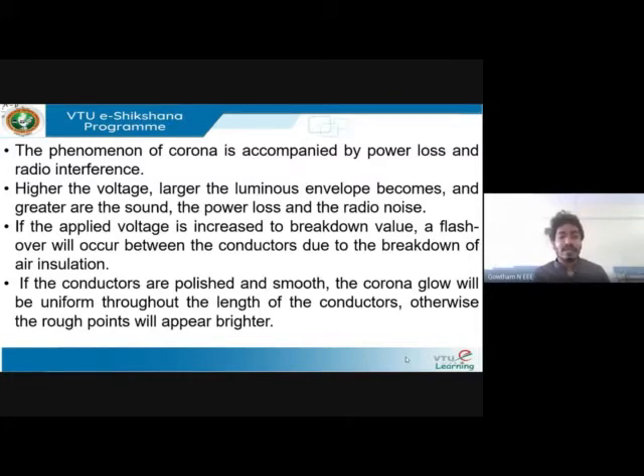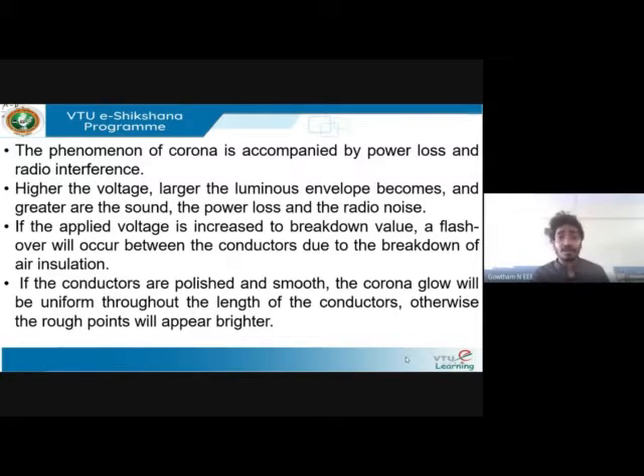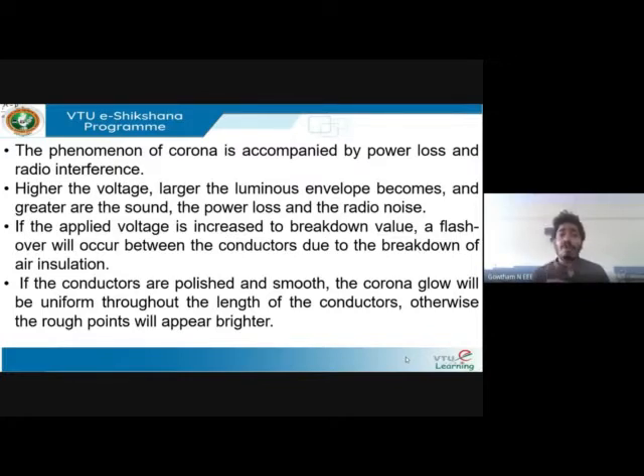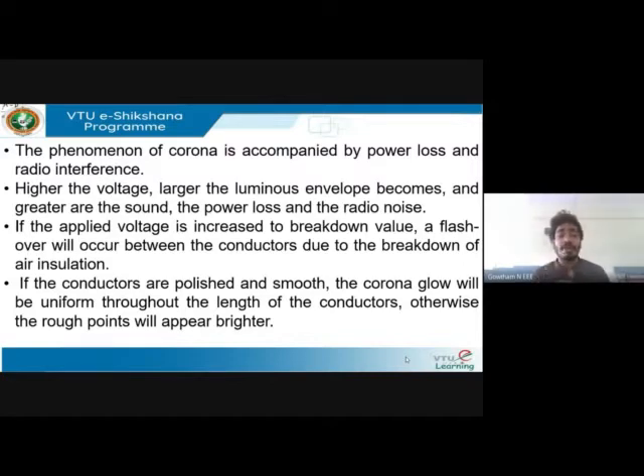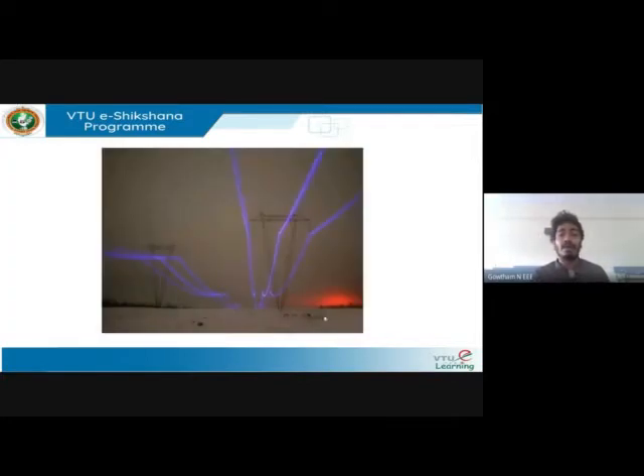This discharge will also affect the insulation of the line. If the conductors are polished and smooth, you get uniform corona glow throughout the length. If the conductors are not polished and have rough points, corona will be more intense and brighter at those rough points. If smooth, it will be uniform; if not polished, it concentrates at rough or uneven points.